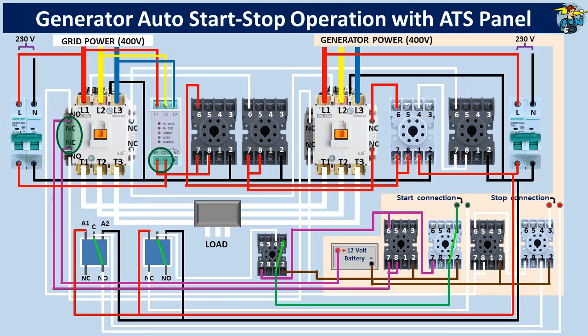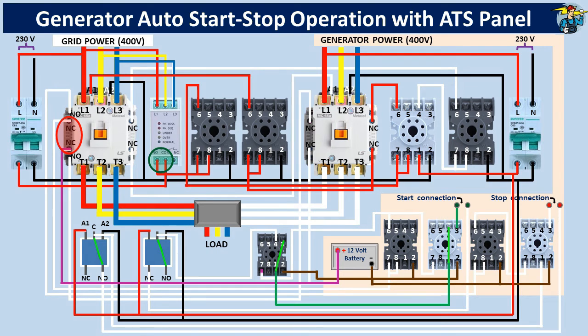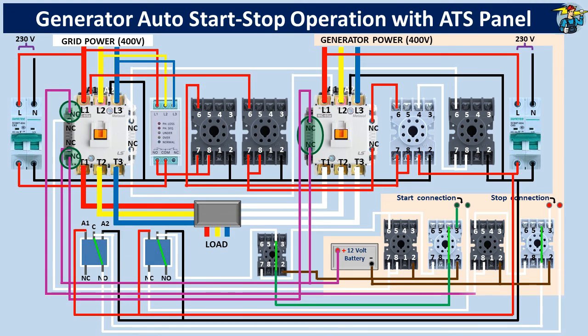This safety time lapse prevents grid power from being transferred to the load immediately after the generator is unloaded. The load is now receiving 3-phase power through the grid side contactor. With it, the normally closed auxiliary contact points of the grid side contactor will open, causing the generator start timer, start relay, and start fail timer relay to lose their 12V supply. At the same time, the normally open auxiliary contact points on the mains contactor will close. Since the normally closed auxiliary contact points of the generator contactor also remain closed, a path is created for the generator stop timer to receive 12V power. Normally, after running at full load, the generator should idle for about 5 minutes before stopping. With only an average load on the generator, 3 minutes on this shutdown timer will be acceptable.